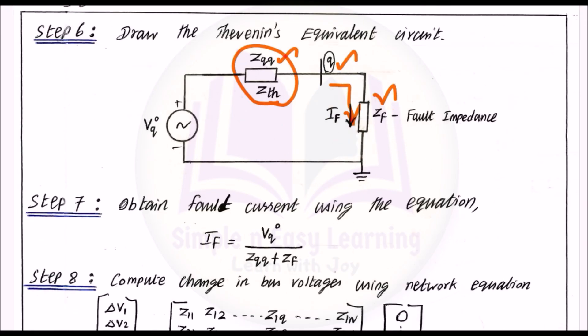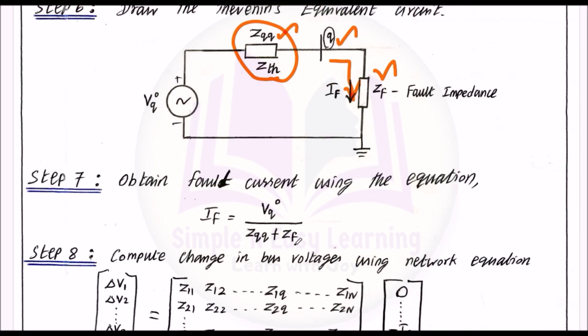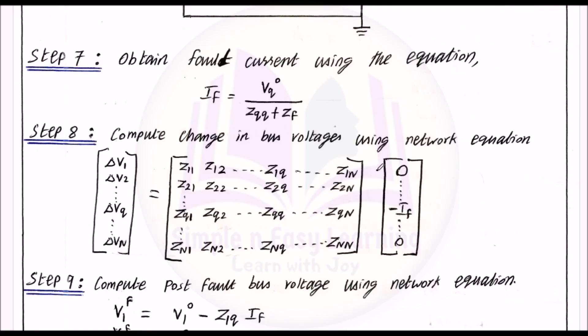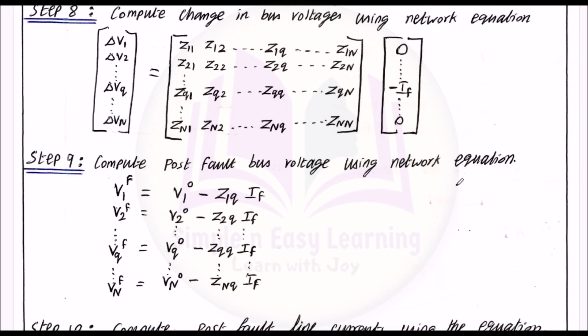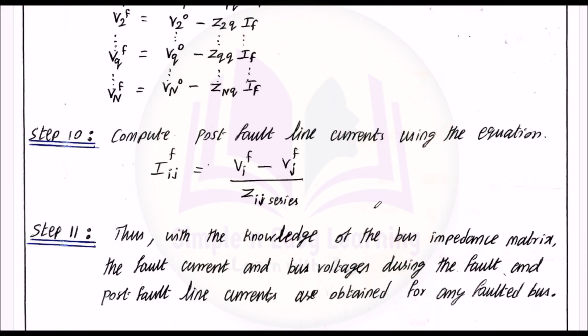Step 7 — obtain fault current using the equation: If = Vq0 divided by (Zqq + Zf). Step 8 — compute change in bus voltages using network equations ΔV1, ΔV2, up to ΔVn. Step 9 — compute post-fault bus voltages using the same network equation seen in the flowchart. Step 10 — compute post-fault line current using Iij = (Vi minus Vj) divided by Zij series. Step 11 — with knowledge of the Z bus matrix, the fault current, bus voltages during fault, and post-fault line currents are obtained for any faulted bus.